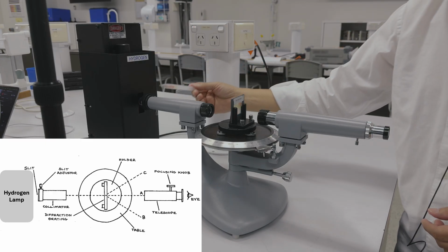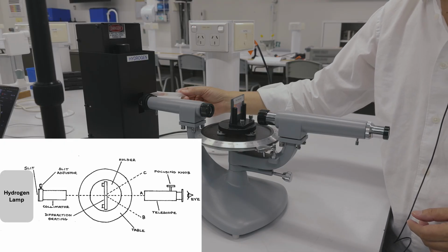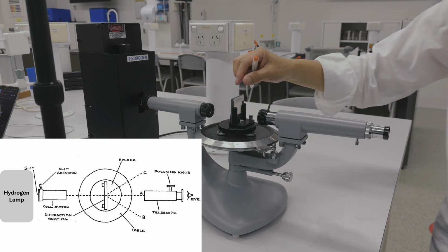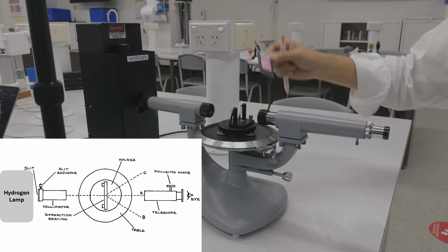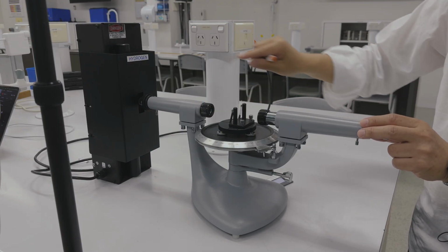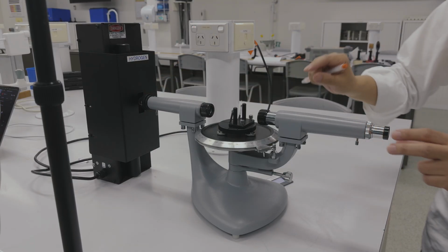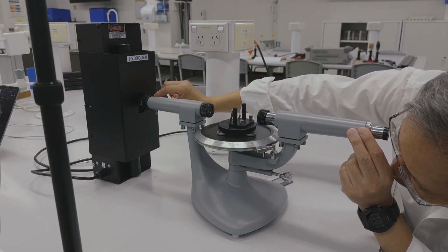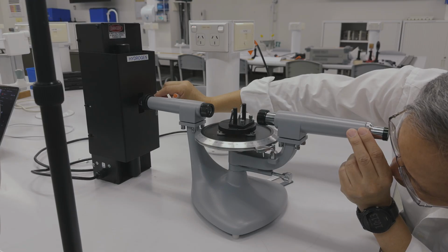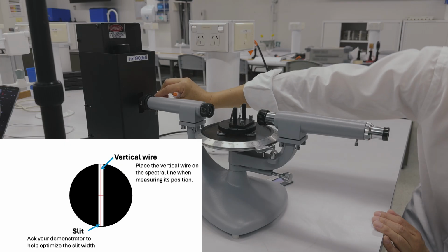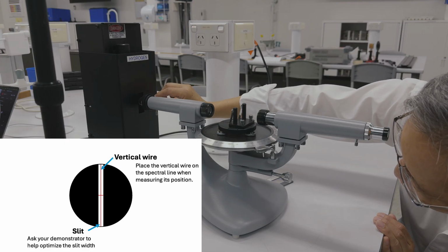We have a gauge or a slit which you can adjust with this knob. Now, I will first remove the grating. Through the telescope, you can find the image of the gauge or the slit here. Now, if you look through the telescope and make your slit at the center of the cross, now you can adjust the width of the slit.